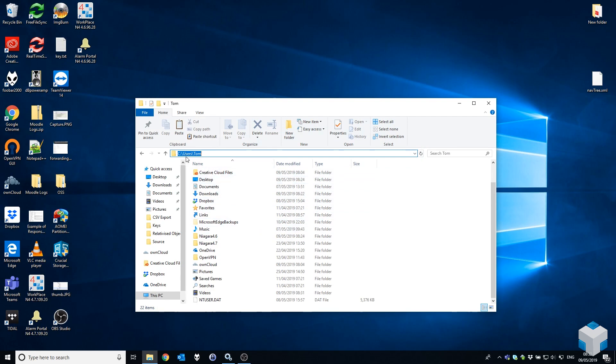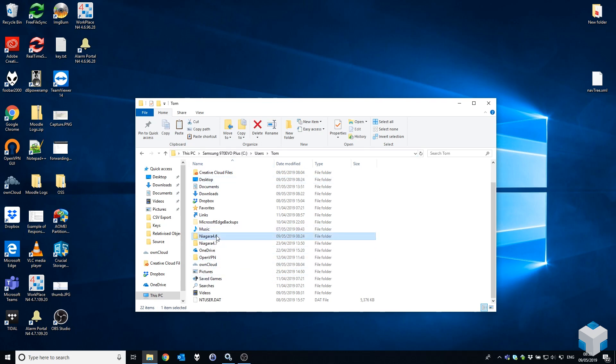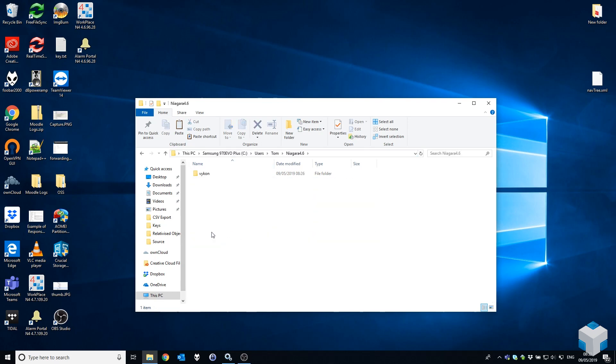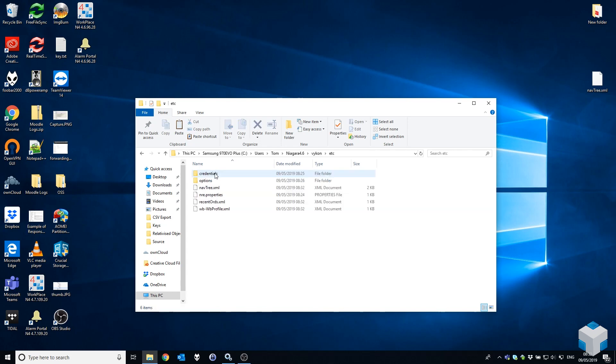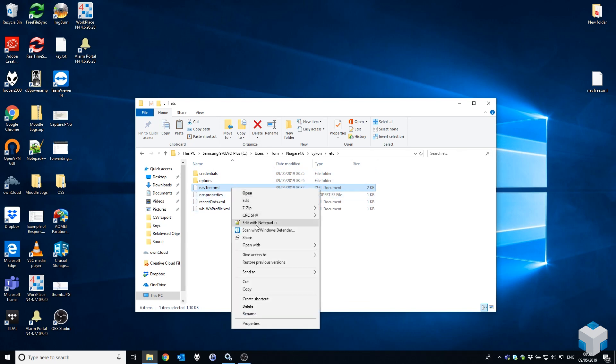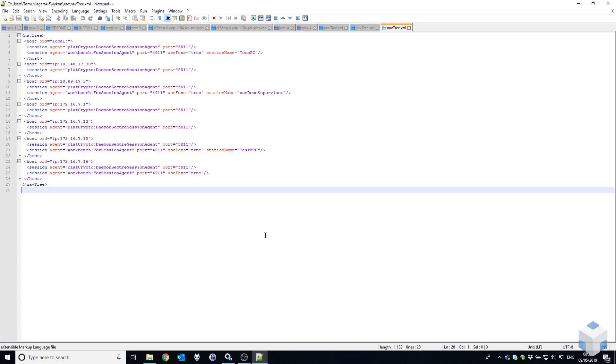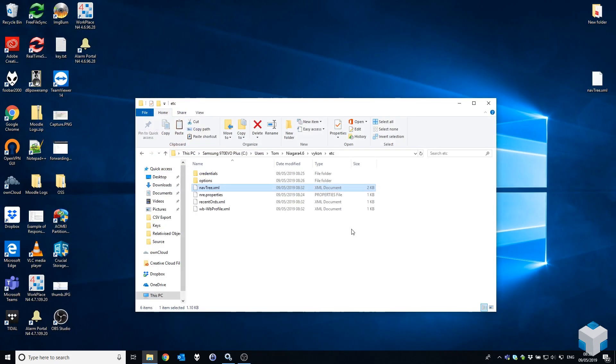Under your users directory in Windows, you'll see users and then your username. I'm going to go into my previous directory, 4.6, into the Niagara folder, into the etc folder, and here you'll see nav tree.xml. If I open that up, you'll see that's where all my connections are stored.